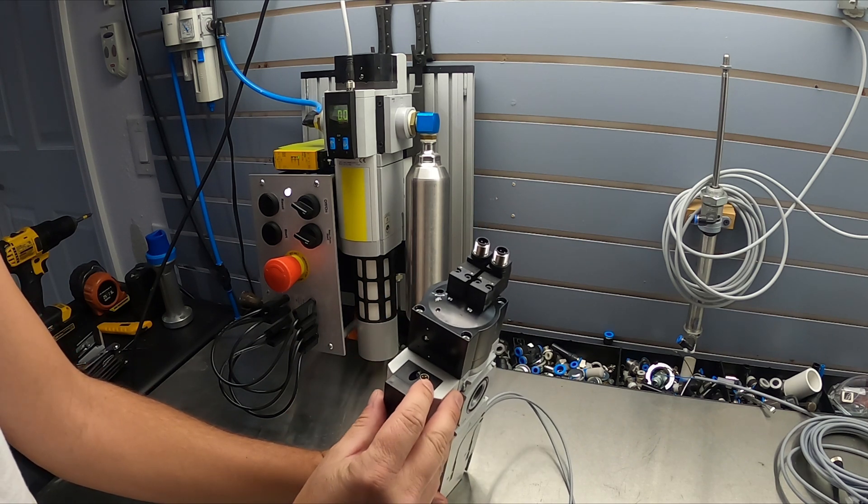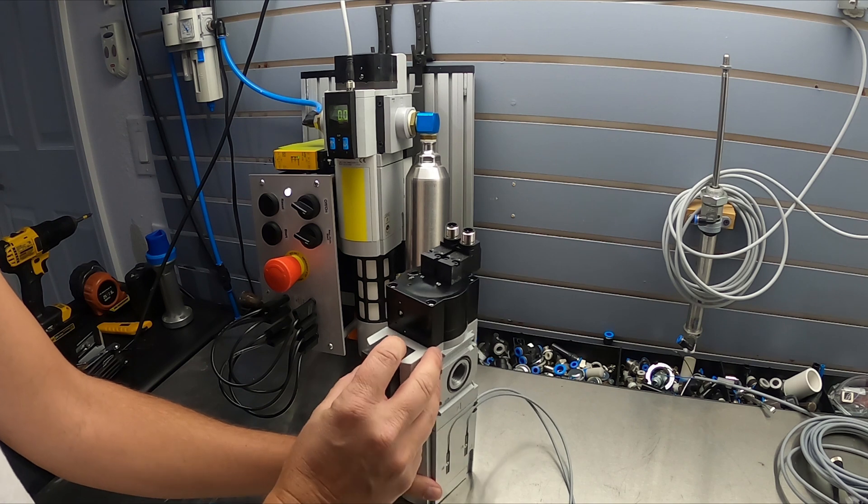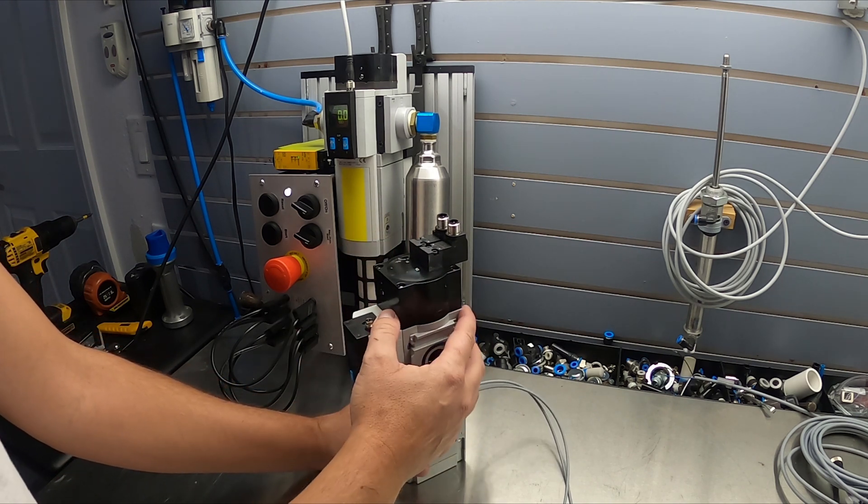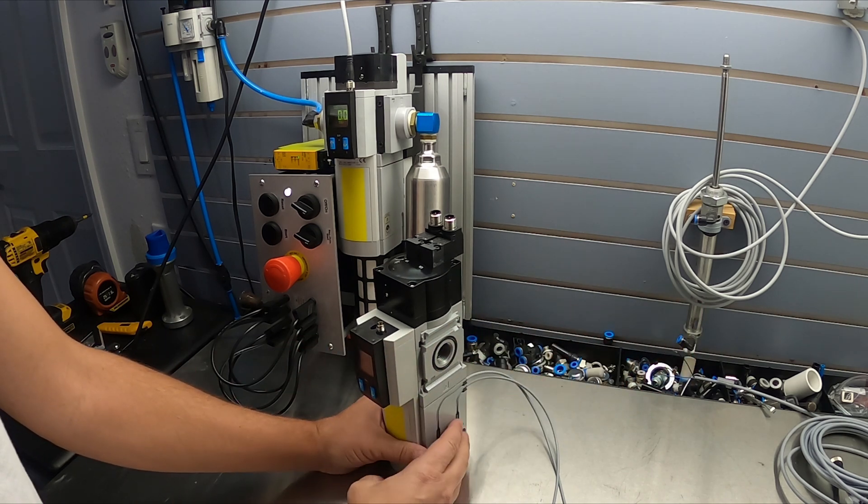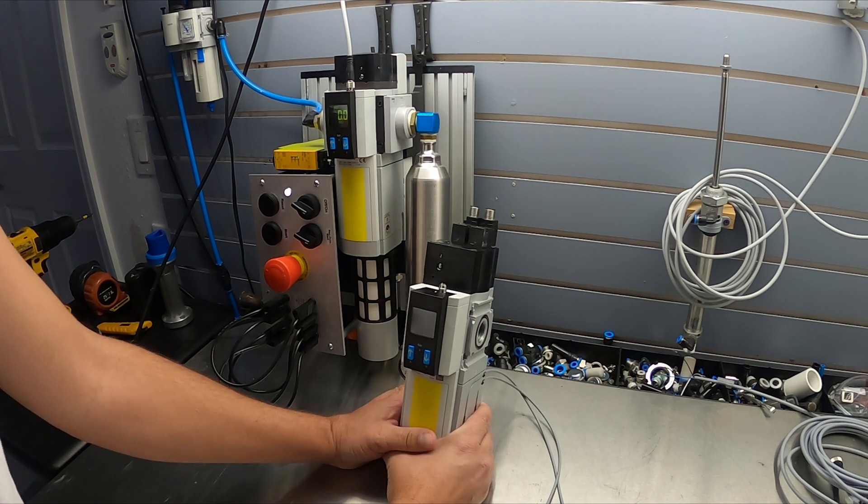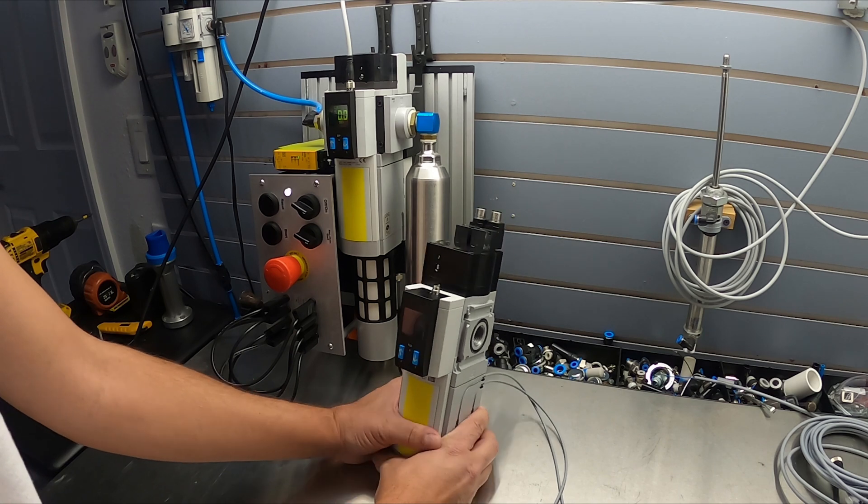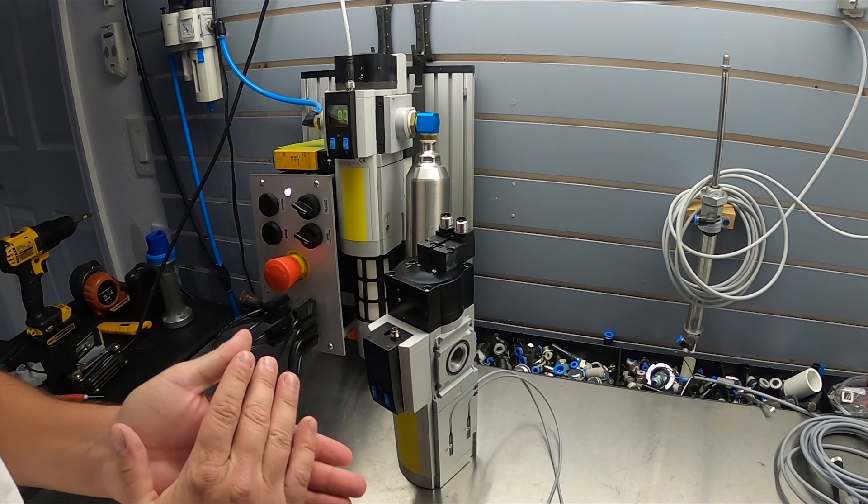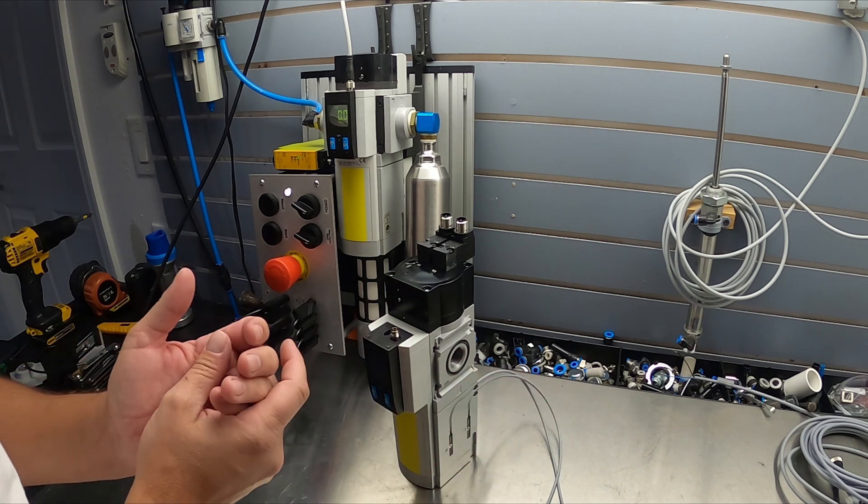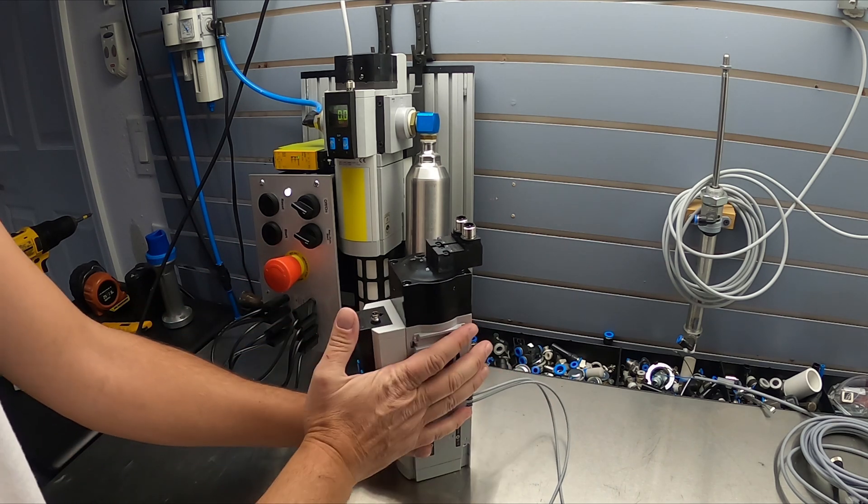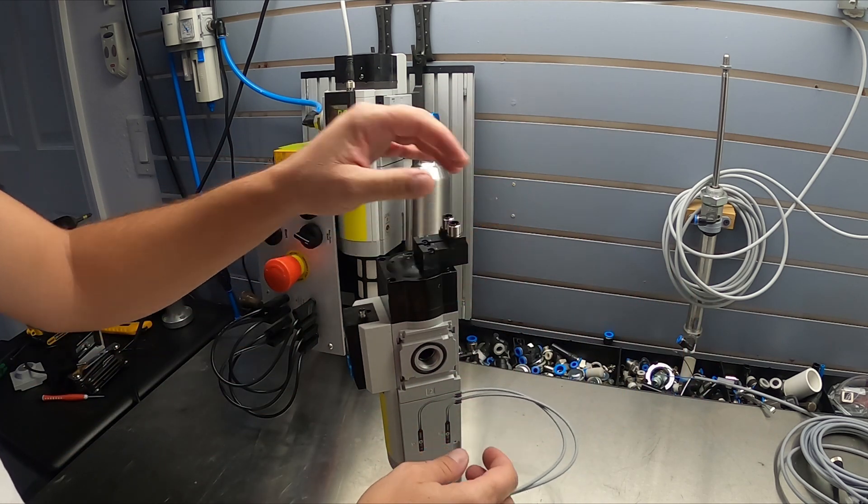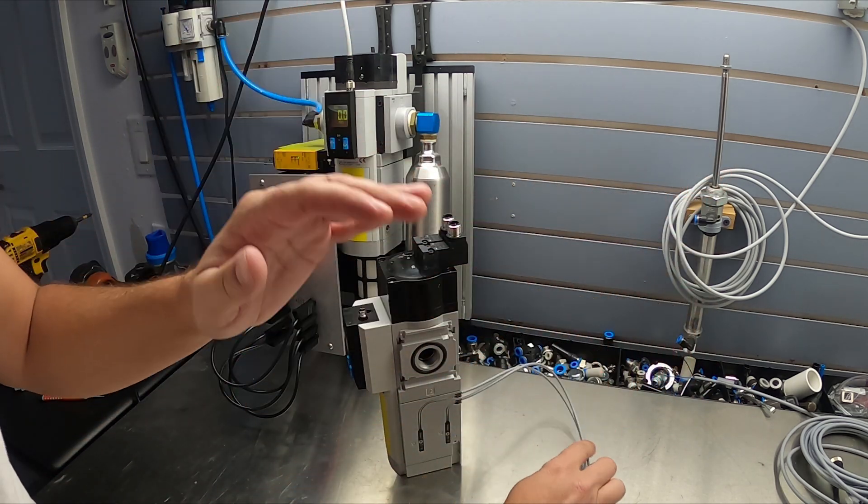And those sensors have two M12 cables as well. And then because this one has an optional pressure sensor on it as well, there's an M8 cable right here that's required. So long story short, you're gonna have to have five cables running off of this device into your panel. It's up to you guys to make it function in whatever category or performance level that you guys need.